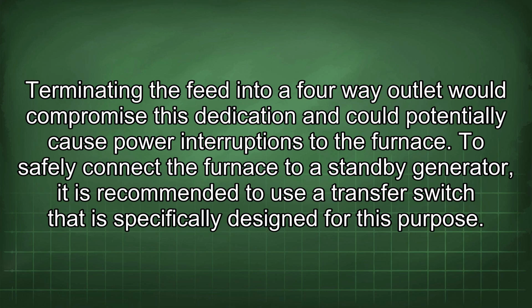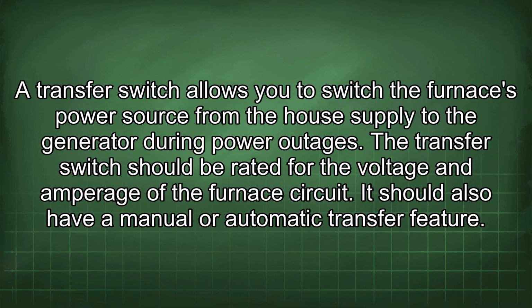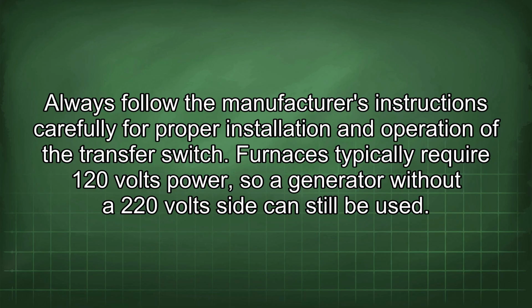To safely connect the furnace to a standby generator, it is recommended to use a transfer switch that is specifically designed for this purpose. A transfer switch allows you to switch the furnace's power source from the house supply to the generator during power outages. The transfer switch should be rated for the voltage and amperage of the furnace circuit. It should also have a manual or automatic transfer feature. Always follow the manufacturer's instructions carefully for proper installation and operation of the transfer switch.